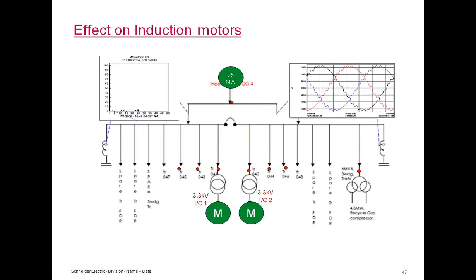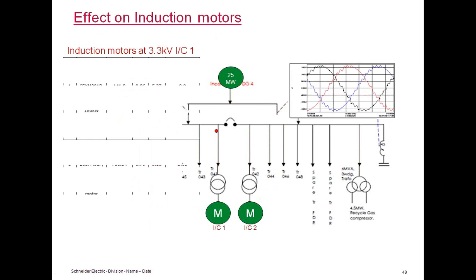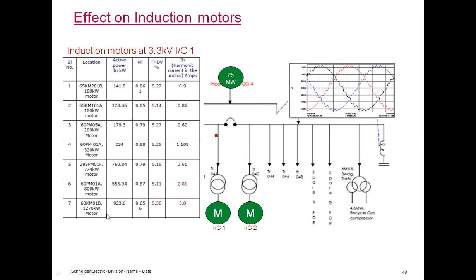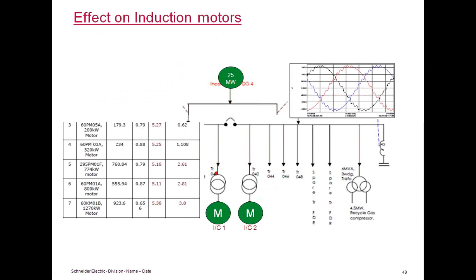He was saying they were replacing motor ball bearings and replacing the windings in the motors at least once in 3 or 4 months or so. So we measured the harmonic current flowing to the induction motors, creating a negative torque on the induction motor, and it's eventually causing premature failure in the motors. Here is a sample of the harmonic current measured. For example, for a 1250 kilowatt motor, the harmonic current is about 4 amperes. In one other case, the harmonic current is 3.8 amperes.